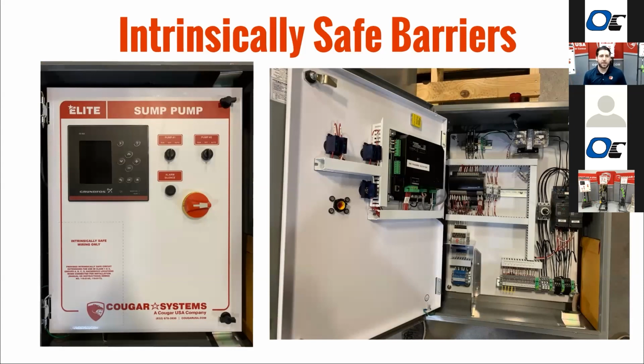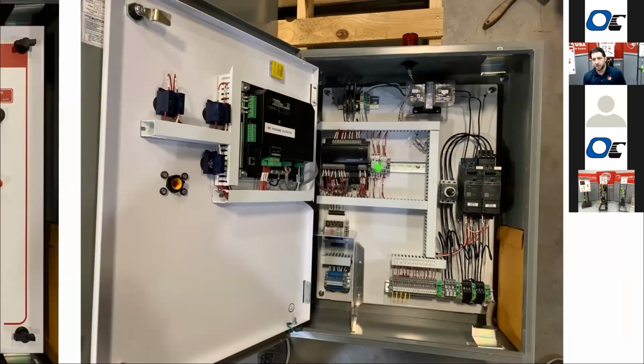Okay, so I do want to hit on the intrinsically safe design here. This is something we've done with Osborne for the sanitary applications where explosion-proof motors are required, and pairing those with the intrinsically safe controls. Grundfos now has the explosion-proof motors available as a standard on the SL pumps, and it can be paired with this control panel here to meet the requirements. So you can see on the outside here, we've marked this area for the intrinsically safe wiring only. And on the inside of the panel, you can see we've created a physical barrier here, as well as having this electronic barrier here.